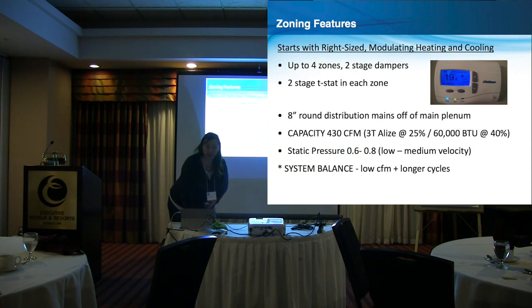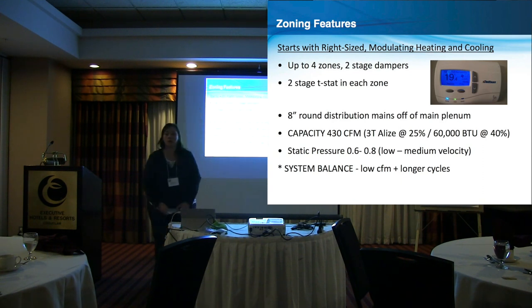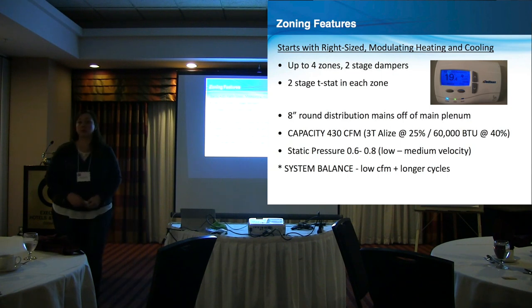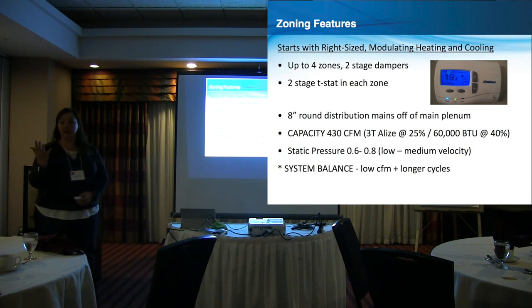Does anyone have any questions while I'm on this? Yes. Just on the zone, if I understood you correctly, basically you're just trying to balance out two zones. We have two extremes. We have up to 4 zone capability on that distribution box, and it's really about driving comfort. With our regular modulating system, we've got 1 thermostat. Now with the zoning system, you put a 2-stage thermostat in each zone and balance the zones with all the algorithms and protocols. As long as there's a 2-stage call, the system will kick in and the zones open up amongst themselves and do their thing. Just distributed.